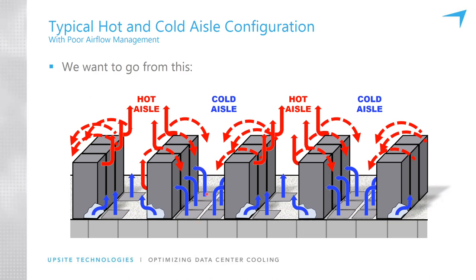So here we have a cold aisle. This is where most of the supply tiles are, and it's really where the only supply tiles should be. But we also have in this example some supply tiles in a hot aisle releasing cold air into the hot air path back to the cooling units. We also have unsealed cable openings, which are releasing conditioned air, and that air flows through the cabinets out the back and again into the exhaust air return path to the cooling units. So it can be very messy.